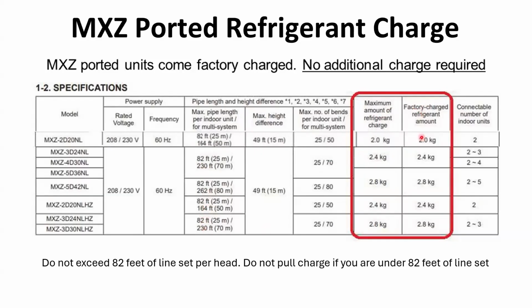What they're showing right here is the factory charge amount. It's going to have the footage in there, and they have it in kilograms right now. But what we're showing is they've added the additional charge into the unit, so you don't have to. It's chargeless systems, is what we're calling that, on some of the units. Still, a lot of the rules still apply. Do not exceed 82 feet of line set per indoor unit. So do not pull the charge if you are under 82 feet. We don't remove charge if you're less than that max piping length, just like before. The only thing that's changed here is they're including the additional amount in the unit now.